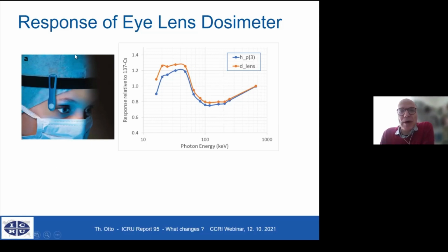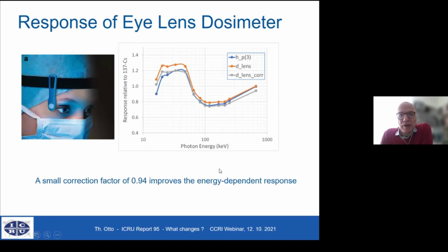And as I said before, at low energies, there is some deviation. But one could, for example, calibrate at the reference point and then use an arbitrary correction factor. And this I have really done by playing around with the curve. There is no fitting algorithm or so involved. When you reduce this by 0.94, you get a very good energy response of this lens dosimeter for the new quantity. So for lens dosimeters, which are good for nowadays quantity for photons, there's a good hope that they will also work with the new quantities.